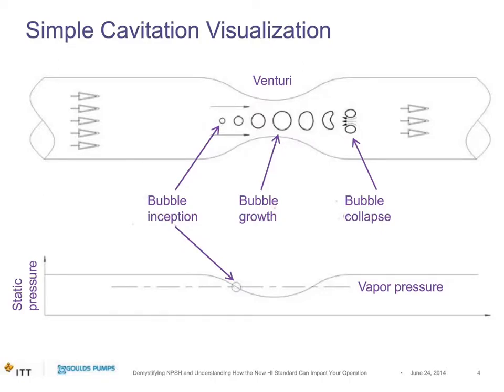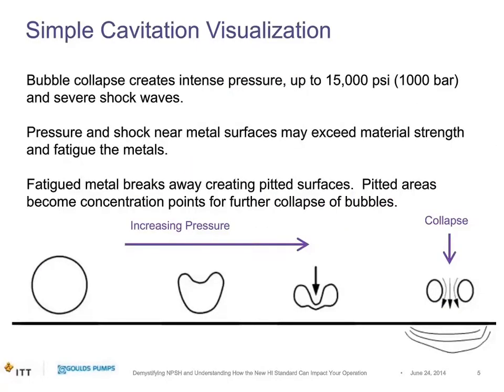Zooming in on bubble collapse: when these bubbles collapse, they create a really intense pressure field — up to 15,000 psi or 1,000 bar, according to Gülich's centrifugal pumps book, with severe shock waves. If these pressure and shock waves occur near a metal or any surface, they may exceed the material strength and fatigue it. That fatigued material breaks away, creating the pitted, matte surface characteristic of cavitation attack. These pits then become concentration points for further bubble collapse as the geometry changes.